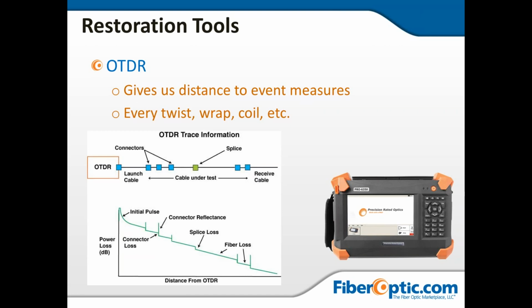So when I'm going in to look at my problems on an OTDR, I'm looking for a loss on a splice or a connector that drops off maybe a dB or more, 2-3 dB, because typically when we're doing any kind of work, 0.75 dB is the allowable loss on a mated pair or a connection. Maybe 0.1 on a fusion splice, if it was done on a V-groove splicer, is acceptable. So if we see losses above 0.75, they're really not supposed to be in the system.